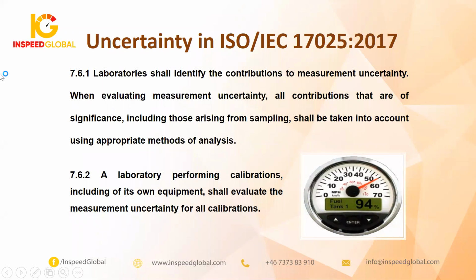We need to introduce a very important point: there is a big difference between uncertainty and error. Sometimes somebody is confused and thinks uncertainty is equal to error. No, there is a great difference between them, because error is the result of a measurement minus the true value of the measurement. If the actual value is 25, for example, and your measurement is 24, the difference between the actual value and your value is the error.